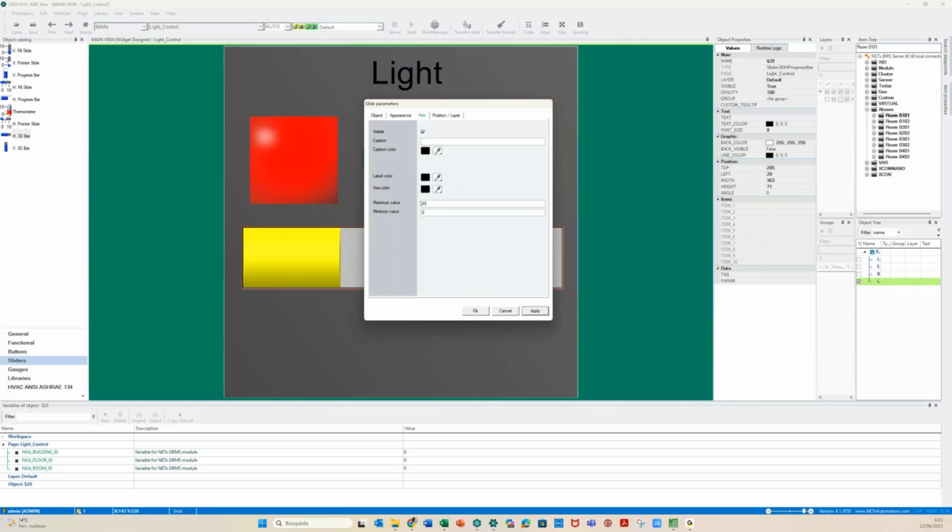And this is why I was telling you to remember to put the correct data point from KNX. DPT 5.001 is scaling. That's the right one. Because if not, your 0 to 100 will only be 0 to 40% if you are not using the right data point. If you are using the default unsigned integer, you will not be able to dim the light using a value more than 40%. Okay, but normally you don't have to think about these issues, but it's important.